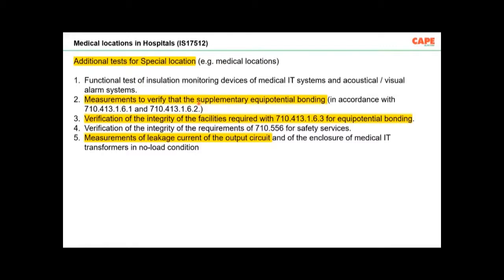Now the standard for the medical location says you are supposed to do the testing of the supplementary equipotential bonding. Verification of the integrity of facilities is required for equipotential bonding. Every standard recommends making equipotential bonding. A good earthing means how good your equipotential bonding is, and the testings are very much documented in all the standard. Now, let us say, for example, a hospital, how to do the testing of supplementary equipotential bonding. Unfortunately, only very few hospitals have made this protective measure. So there is nothing to test because the safety measure itself is missing in most of the places.